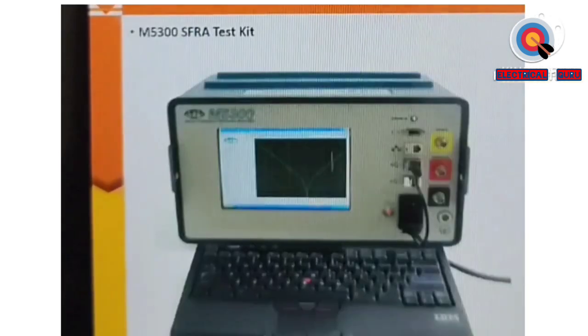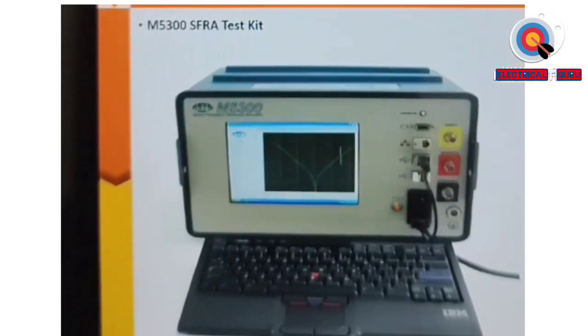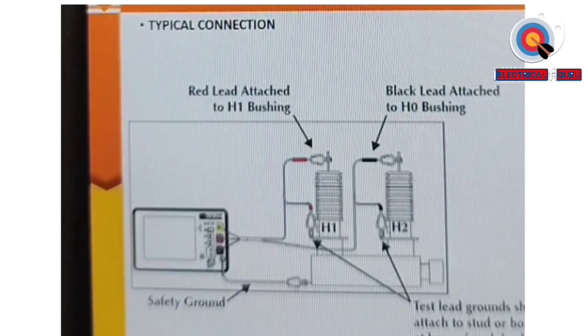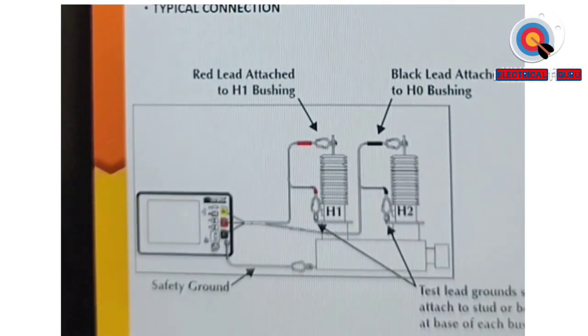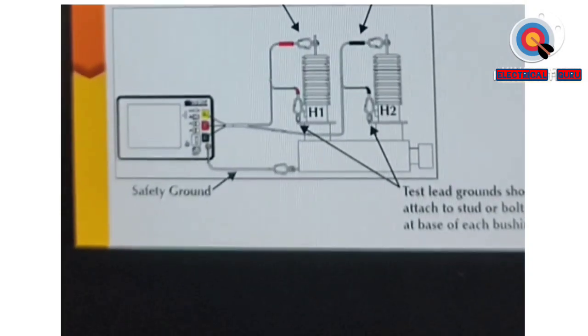So this is the equipment through which we carry out this test. So here you can see we have H1, there is a red lead attached to the H1 bushing, and a black lead which is attached to the H0 bushing. The test lead ground should attach to the stud or bolt at the base of each bushing. So this is how we measure.